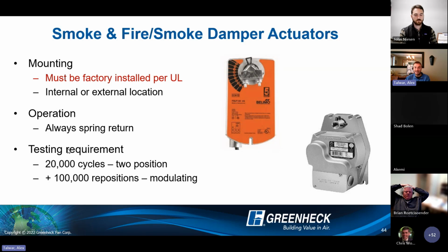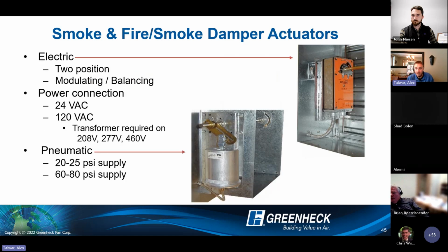And before we can do any of that, we actually have to do a cycle test on the damper and actuator. So make sure that the actuator has enough torque to operate that damper for 20,000 full open and closed cycles. And in the case of modulating actuators, it's got to do an additional 100,000 reposition cycles. So 10,000 cycles from 0 to 10%, 10,000 from 10 to 20. Takes a long time, right? I think it's like 3 months for something like that until you even got a test sample you can throw up on your air chamber.